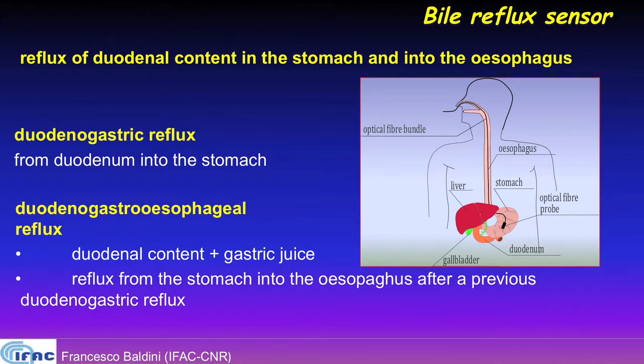Bile is generally secreted by the liver and can come back to the stomach or to the esophagus, creating damage to the mucosa of the stomach or the esophagus. So it's very important to have continuous monitoring. And we use the optical approach exploiting as a marker bilirubin, which is one of the pigments contained in the bile.